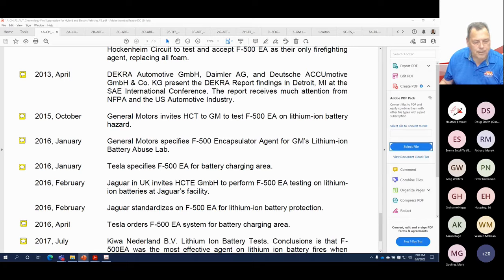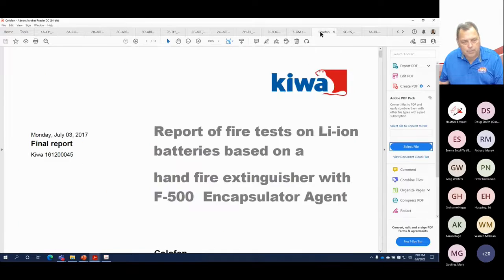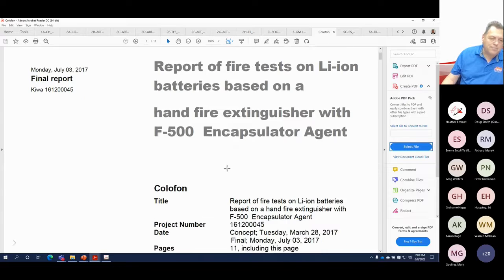I just want to show a little bit about what the encapsulator agent is doing. So on the lithium-ion battery, what's separating the F500EA from other items like foam and dry powder is, one, we're encapsulating the electrolyte, rendering it non-flammable and non-ignitable. And secondly, we're rapidly reducing the heat, and the heat stays reduced to protect against burn back resistance and thermal runaway.